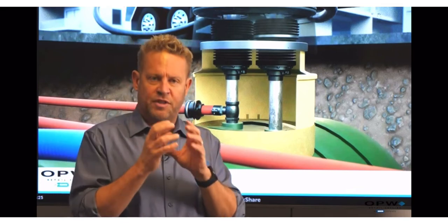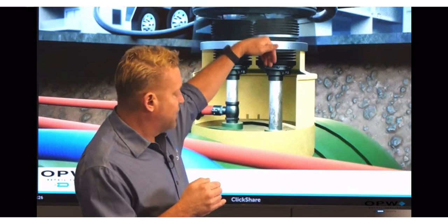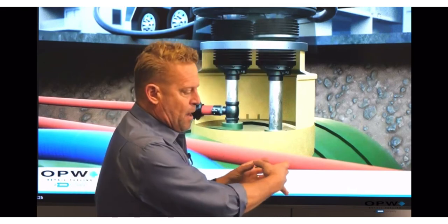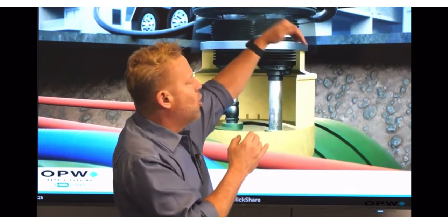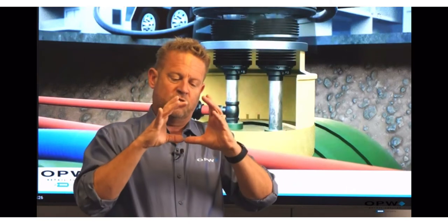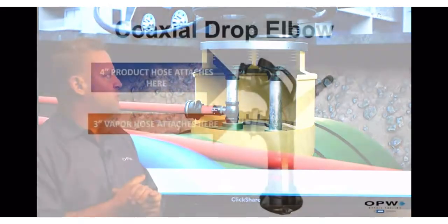On a single point, the fuel drops down the center and the vapors come up on the outside of our riser or drop tube, and then they go back through the hose. Again, the hose has in the center fuel and the outside is vapor, so they collect them through a coaxial drop tube. I actually have a graphic here that shows what that coaxial drop tube looks like. You'll see the two hoses that kind of come up from there.